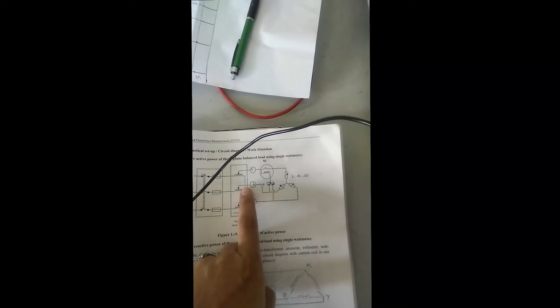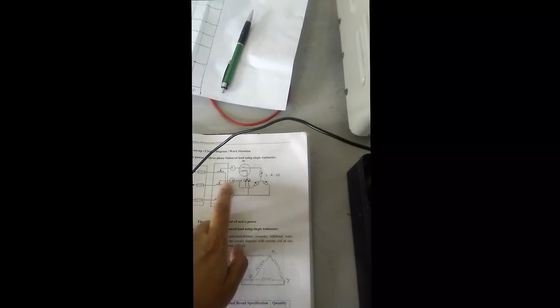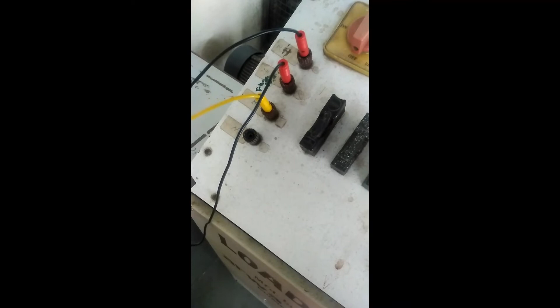Next you have to connect the Y terminal. I am using only one ammeter here, because for a balanced load in three phases the same current flows, so you can connect only one ammeter. Y is connected to the V terminal of the wattmeter, and this V terminal of the wattmeter is connected to the Y terminal of the load, and the B terminal of this auto transformer is connected directly to the B terminal of this load. So this is your resistive load bank.